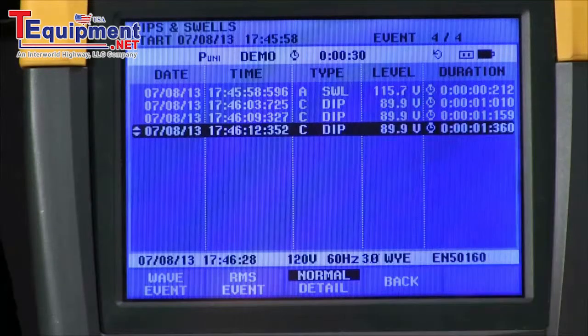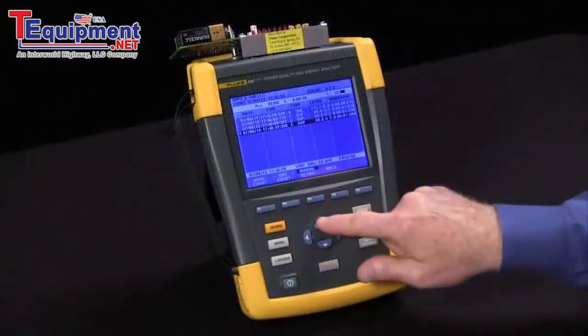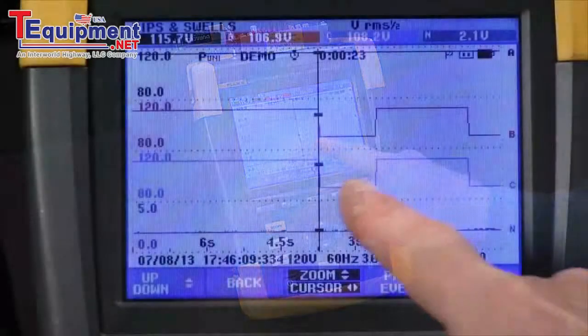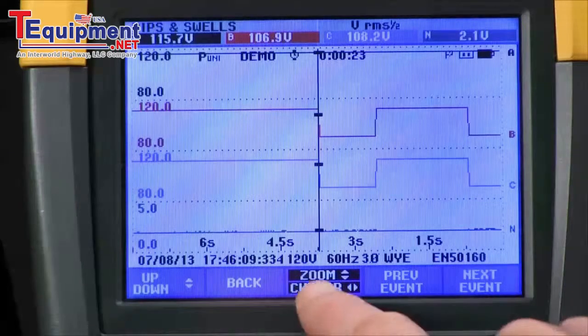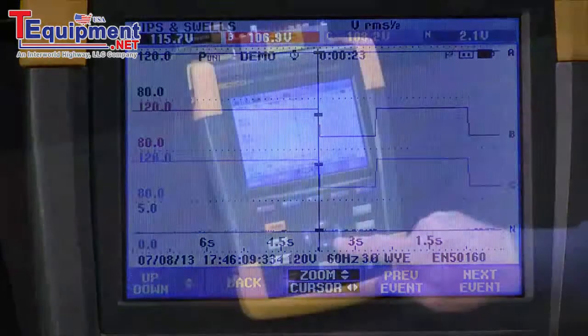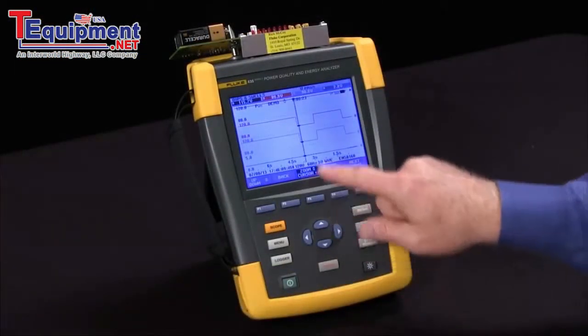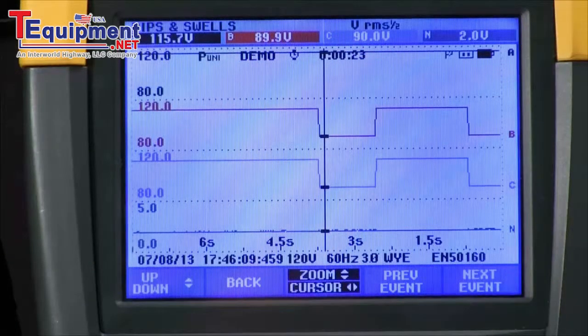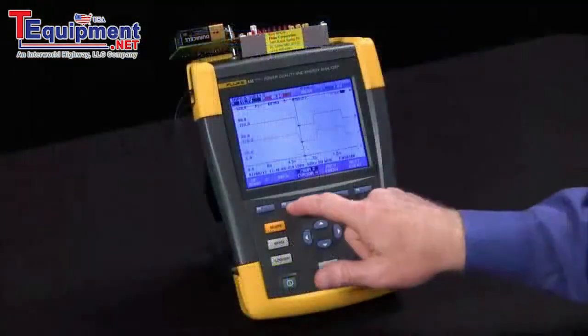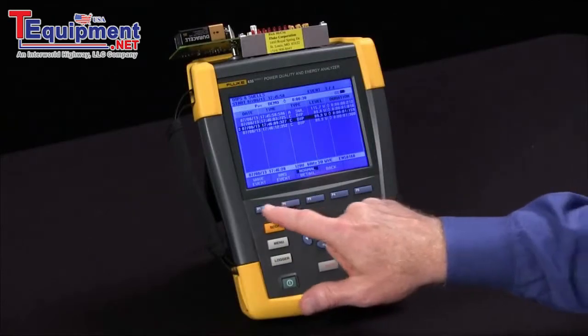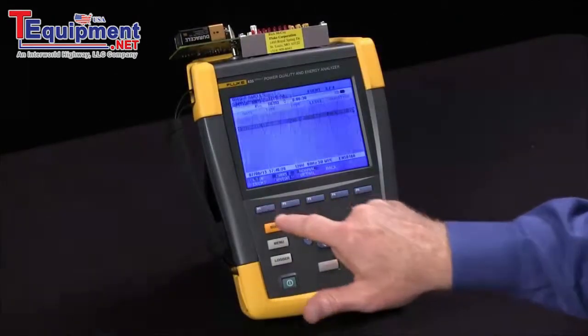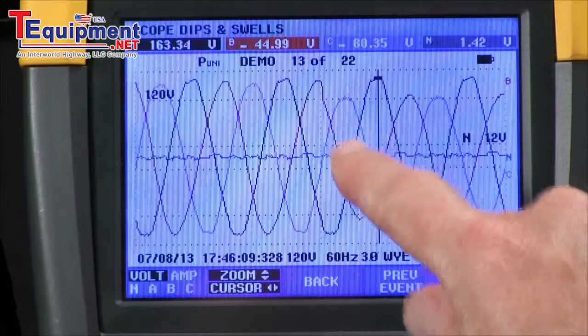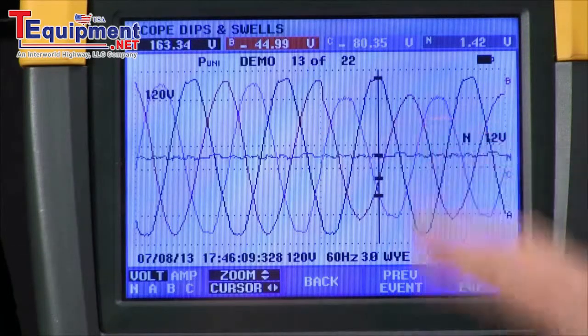If you want to see the trend for a particular event, you simply highlight it and hit the RMS event button, and you can see where that dip occurred. You can use your cursor control to highlight something and see the actual measured voltage at that point. For even more detail, hit the wave event button and you see the actual waveforms — including the actual dips that occurred on the B and C phase.